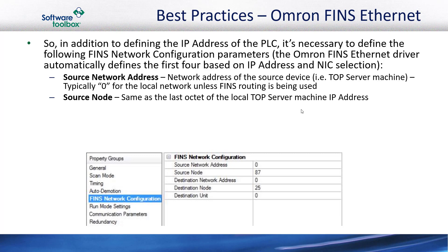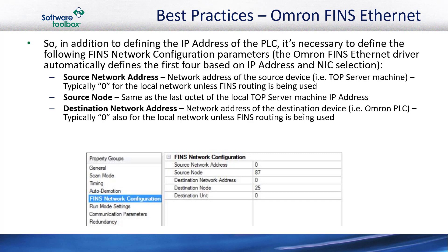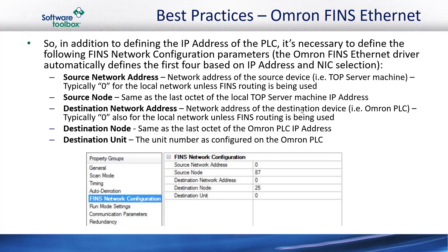The source node will be the last octet of the IP address assigned to the NIC on the TopServer machine. Then we have the destination network address — that's the network address of the destination device, i.e. the Omron PLC. Again, typically zero is used for the local network for this parameter unless FINS routing is being used. The destination node is the same as the last octet of the Omron PLC's IP address. Then we have the destination unit, and that's the unit number as configured on the Omron PLC — which, depending on the model, could be configured either in CX Programmer software or via rotary switches on the physical Omron PLC.